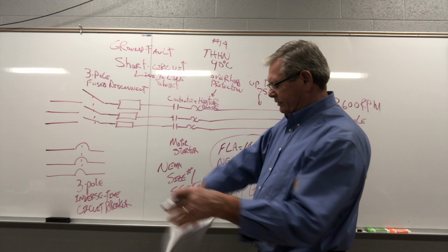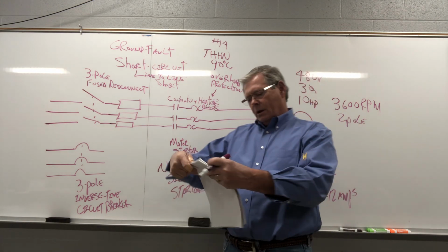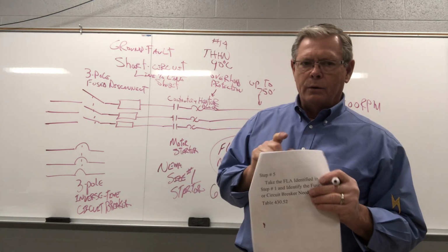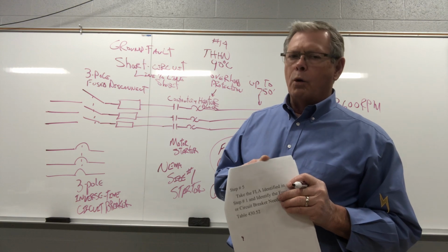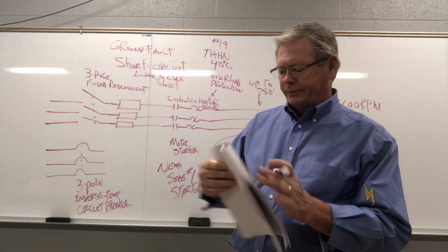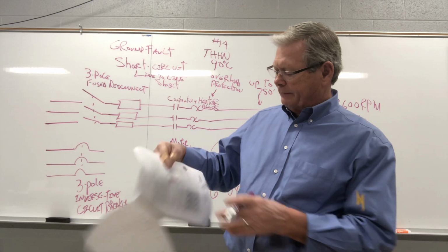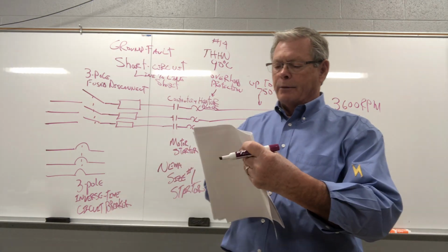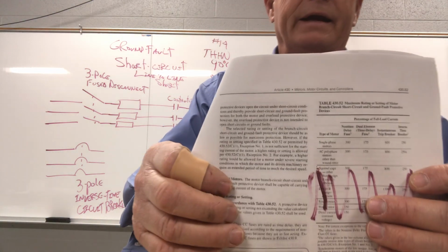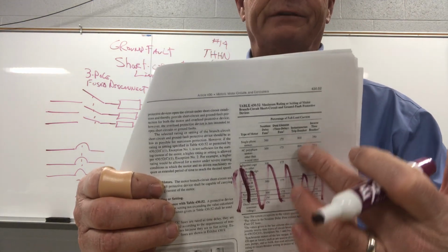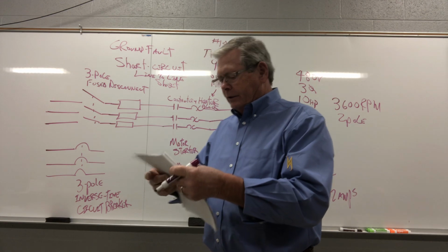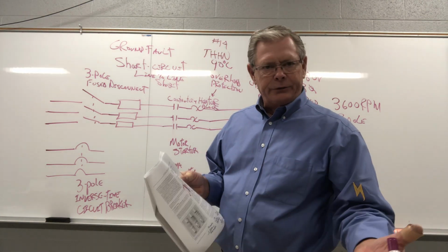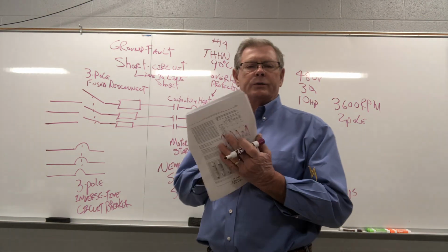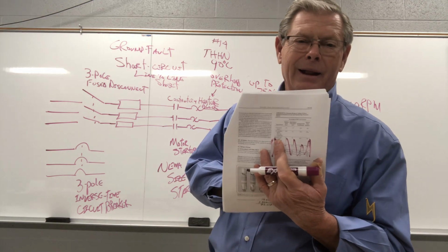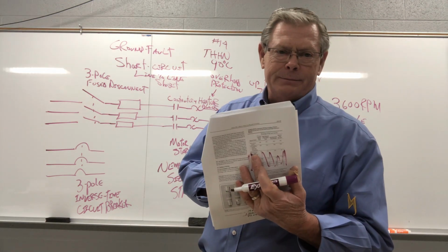Now we move to the next step. We're going to identify what size fuses or breaker we need for this. This comes off of table 430.52 right here. Now, I marked this part out here. You don't need that. You just need the top 2 rows. The top row is single phase. This is 3-phase motor. The second row says AC polyphase. Poly means many. So that's a 3-phase motor.